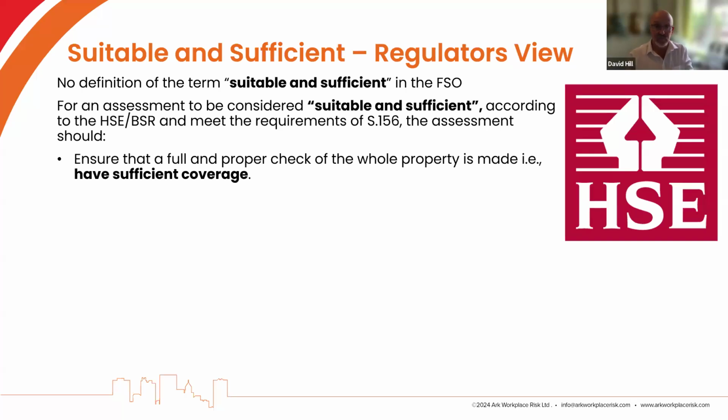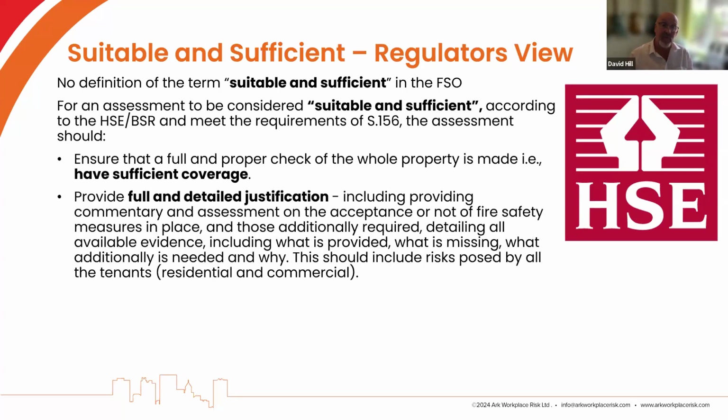And that coverage is really important because we need to actually understand where the risk of fire will emanate from and what preventative measures are in place to prevent that spreading into other areas of the building. Then it's got to provide a full and detailed justification of the fire safety arrangements that are in place. We can't just say, for example, fire doors are in place. Well, what type of fire doors? Where are they? What are they doing? Who are they protecting? So we've got to provide commentary.